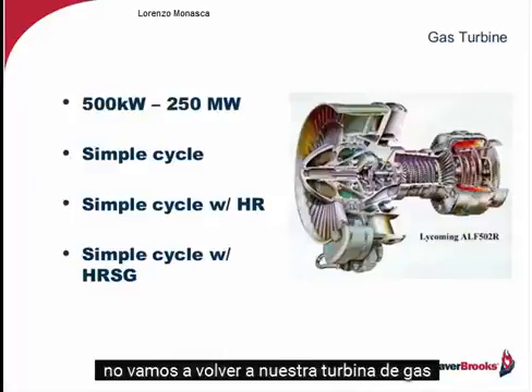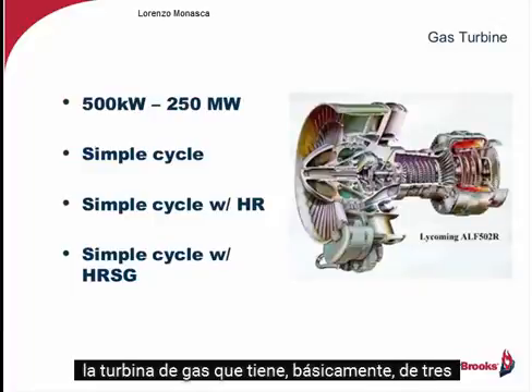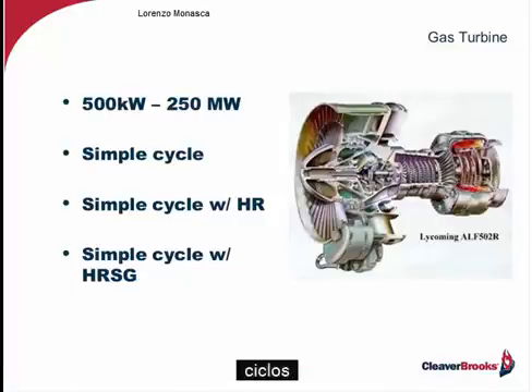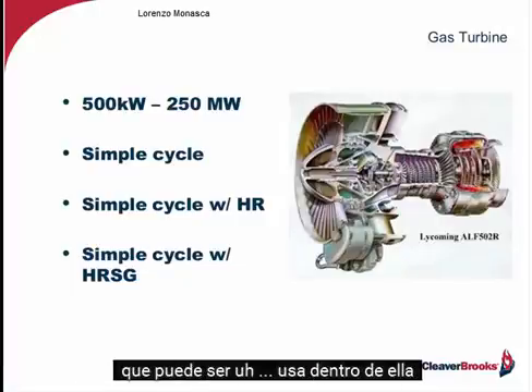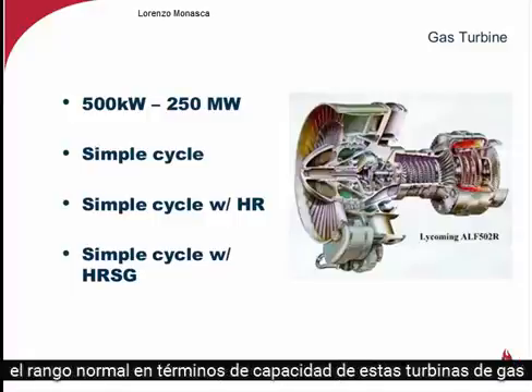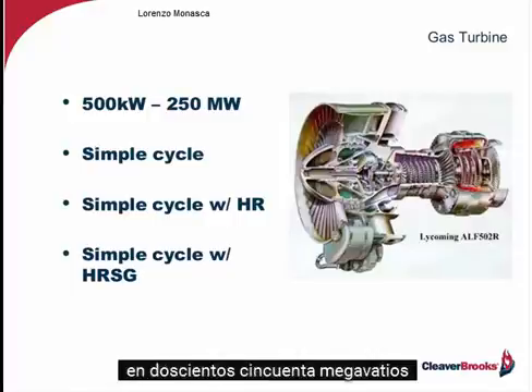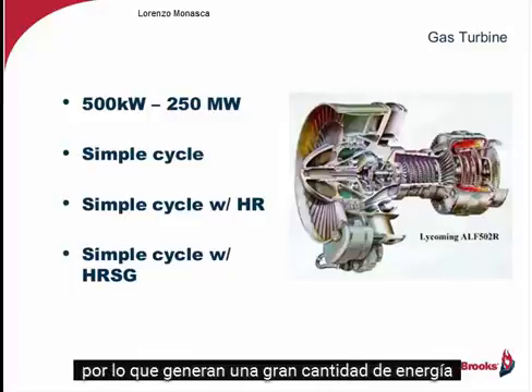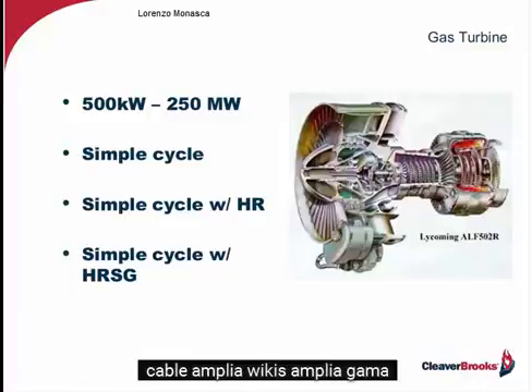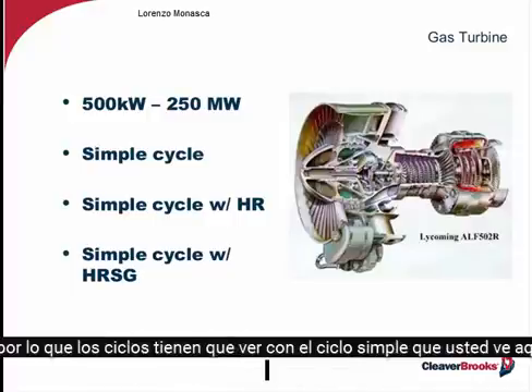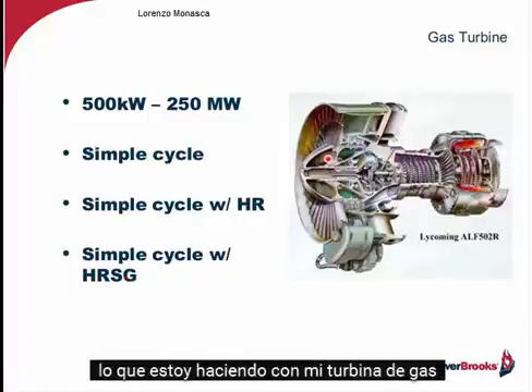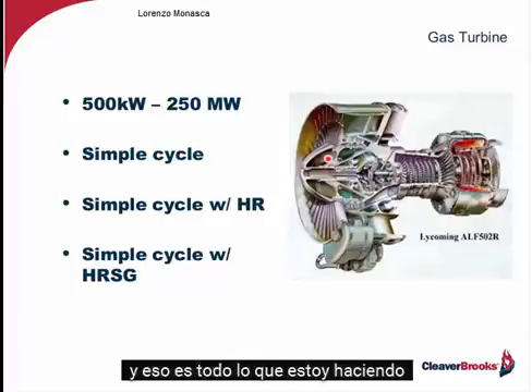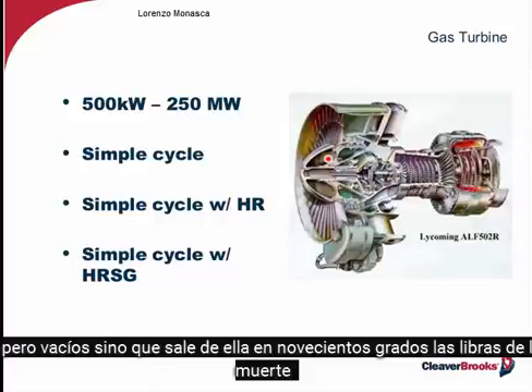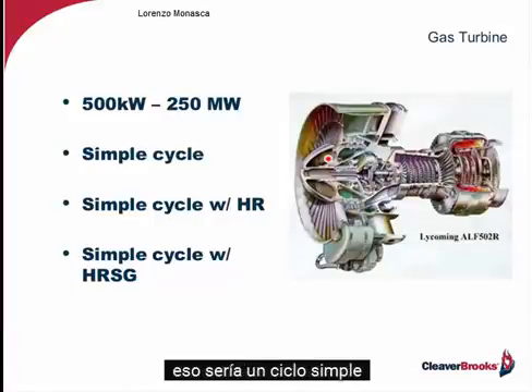Now, going back to our gas turbine. The gas turbine has got basically 3 cycles that can be used within it. And by the way, as you can see on the screen too, the normal range in terms of capacity for these gas turbines is between 500 kilowatts and 250 megawatts. So they generate a lot of power, okay? A wide range with these gas turbines. As far as the cycles are concerned, the simple cycle that you see here, what I'm doing with my gas turbine is I'm driving a generator, and that's all I'm doing. The gas that's coming out of it at 900 degrees, the pounds of gas, is being wasted. That would be a simple cycle.